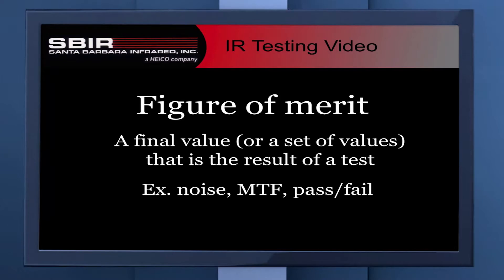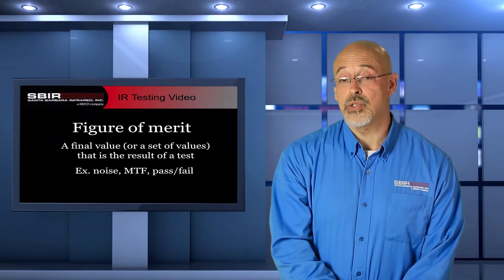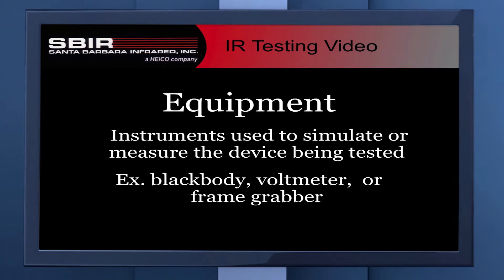A figure of merit is a final value or a set of values that are the result of these tests, and they usually have standardized names — things like SITF or MTF — and these are the final figures of merit that you're going to get from a test on a camera. The equipment should be a set of instruments that are defined before the procedure begins and are calibrated so they can reliably and repeatably produce results when actually taking measurements on a camera.